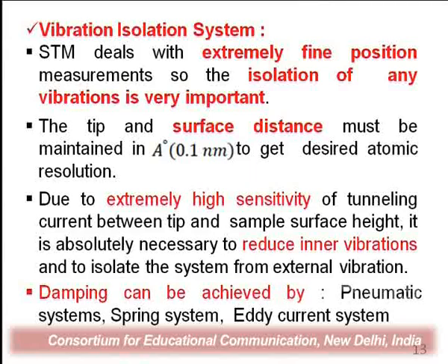Due to the extremely high sensitivity of the tunneling current to the tip and sample surface height, it is absolutely necessary to reduce the inner vibrations of the tip, and to isolate the system from external vibration.